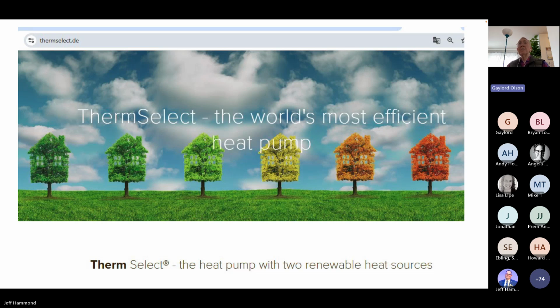So you could ask them, what's the average source temperature that they provide for their system? Or how it would relate to the COP or seasonal performance factor? What's the best they can do? They'd give you some answer, and you'd respond, well, I could do something better than that. Very simply, if you want heating, you can have a very large solar thermal array and a very large water tank, so your system's water temperature can be pretty much whatever you want. The only problem is somebody has to pay for it. So it would be more meaningful if they could claim they're the most cost-effective heat pump in the world, but I don't think they can claim that.